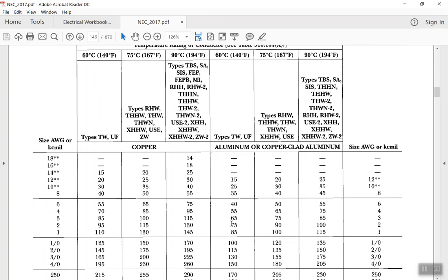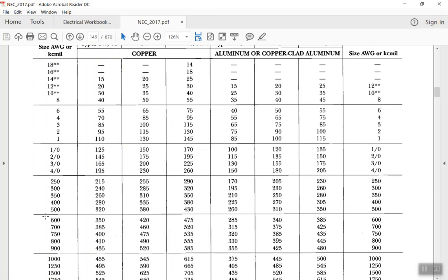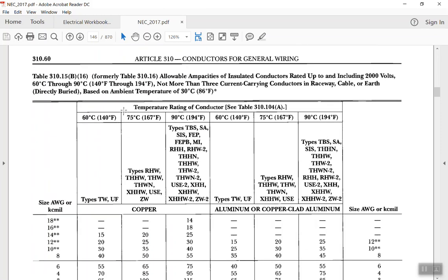Now, if we look up the 400 amps, right, we should be able to see that it lines up with a 600 kcmil. So down here, 400 amps, right? And we're going to go ahead and assume that we're going to use 75-degree terminations. By the way, that is something that you should really just circle big time. Put a big old circle around this because you want to default here. Now, if you're given NM, you might want to write NM up here for non-metallic sheath cable, right above the UF.